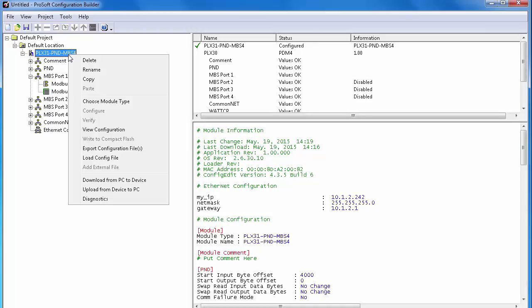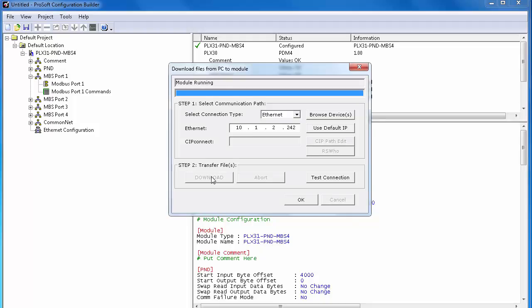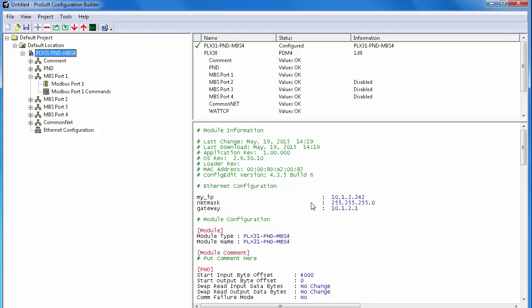Now that the ports on both the Modbus RTU network and the PROFINET network are configured, we can download the configuration to the gateway. Right click on the module's name and choose download from PC to device. On the download screen, confirm that the IP address that we assigned the gateway is in the address field and click download. And that's all there is to it.